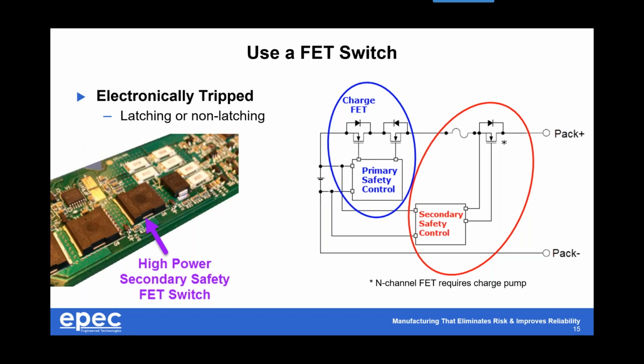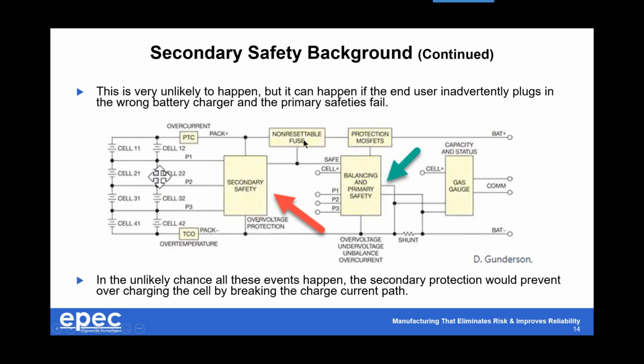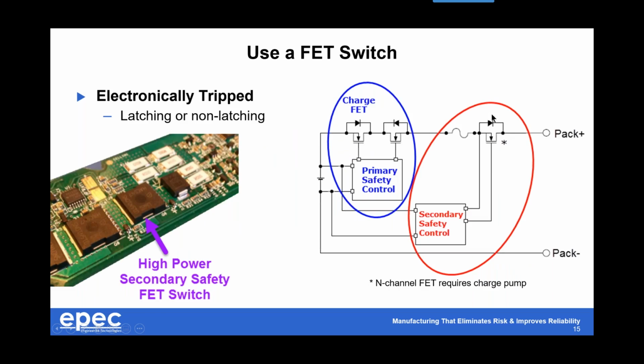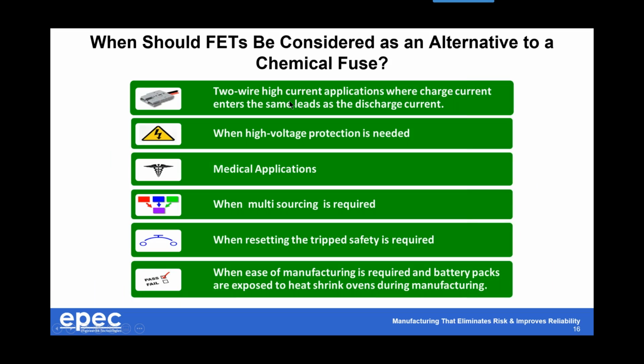We'll often want to use a FET switch in place of a chemical fuse. Going back to the non-resettable fuse on the last slide, that's not always practical to use. So in almost all of our designs, we use a FET switch in place of that fuse, because it acts like a fuse. There are cases where you can't use a chemical fuse, but you still need the secondary safety functionality it offers.